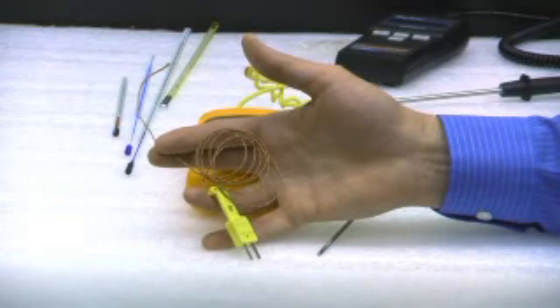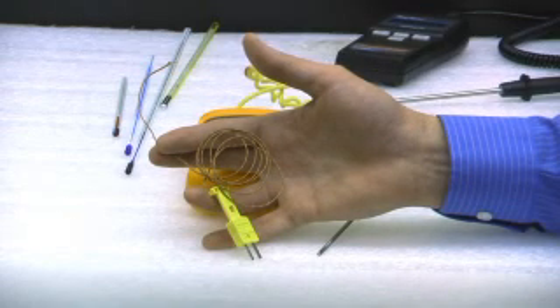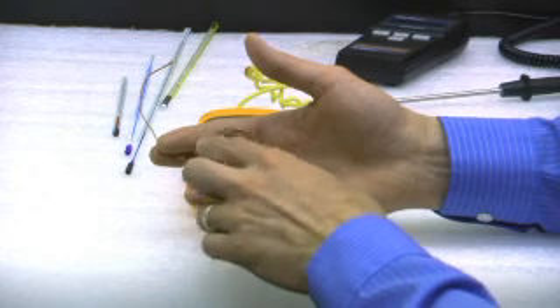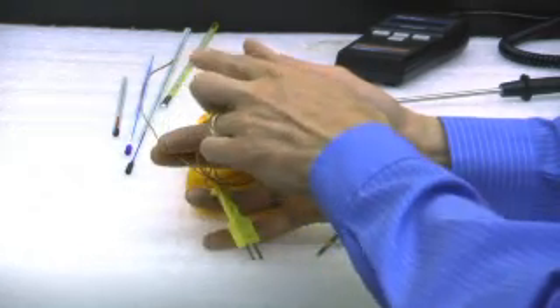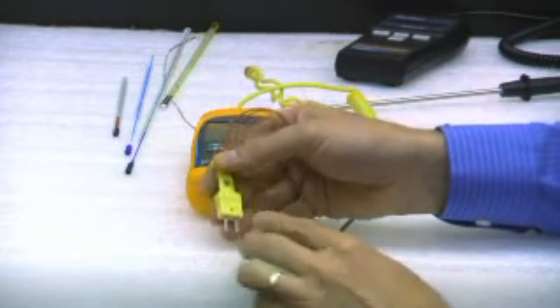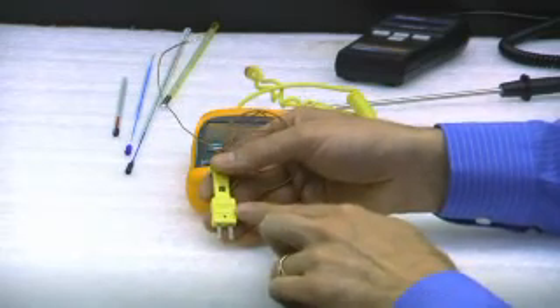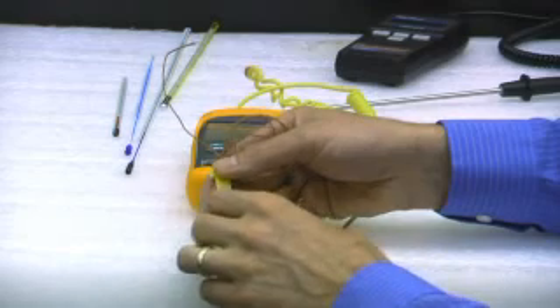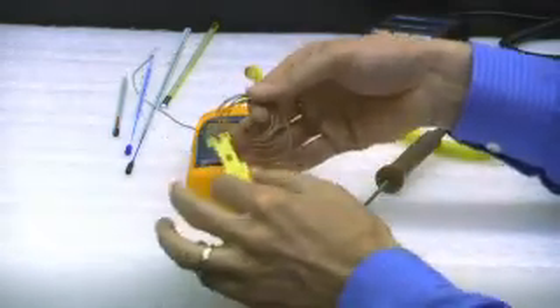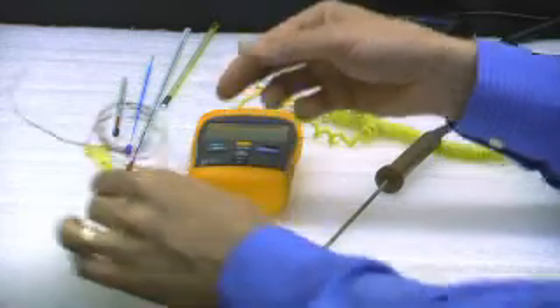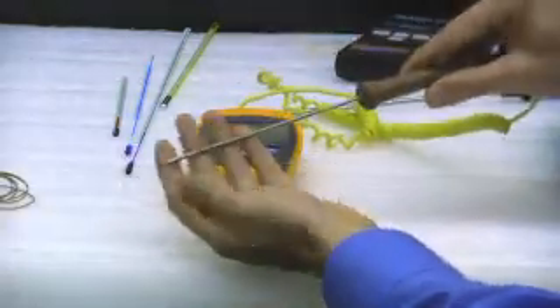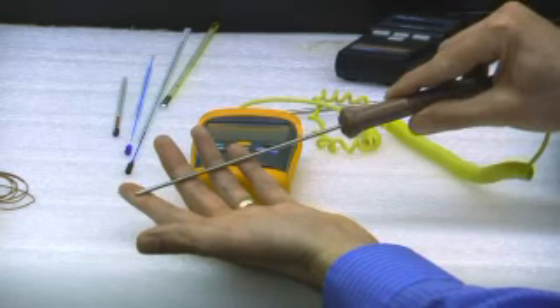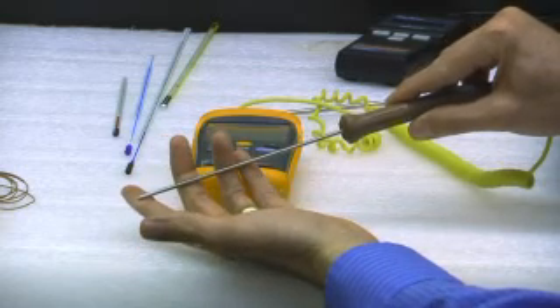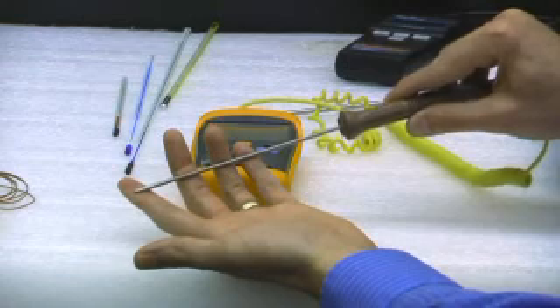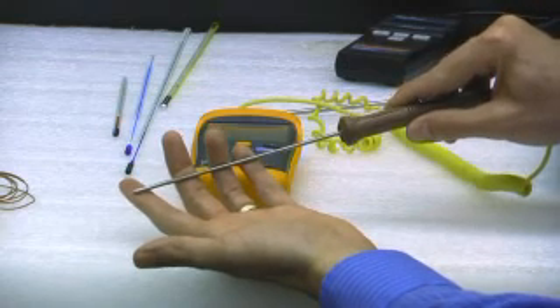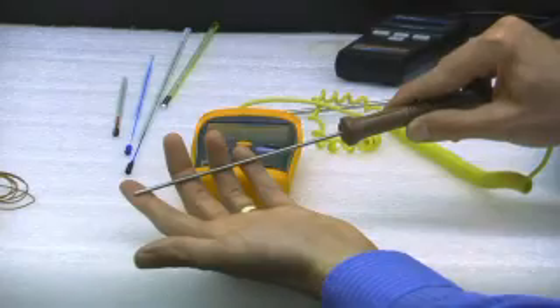A third type of sensor is a thermocouple. A thermocouple is a very simple probe. It's just two wires joined at one point, the measuring junction. Thermocouples are special. You need to use special connectors with the right type to match the wire that you use. They're available as wires like this, but you can get thermocouples also mounted in metal sheaths. Thermocouples are very rugged. They're the most rugged sensor. Their uncertainties are often not as good as the PRTs or thermistors.